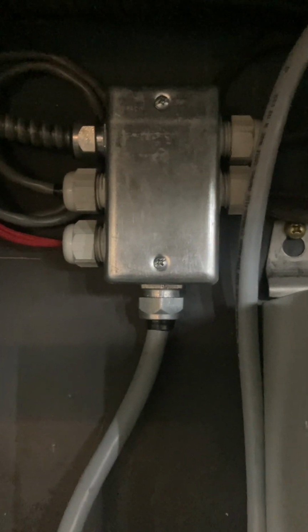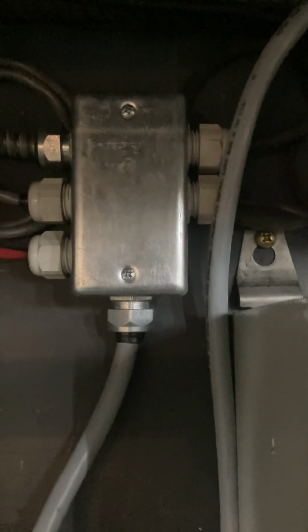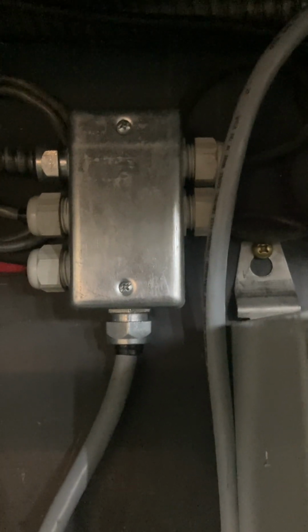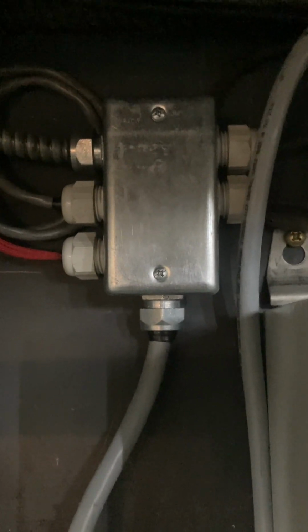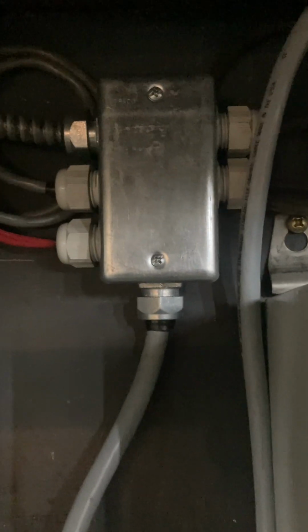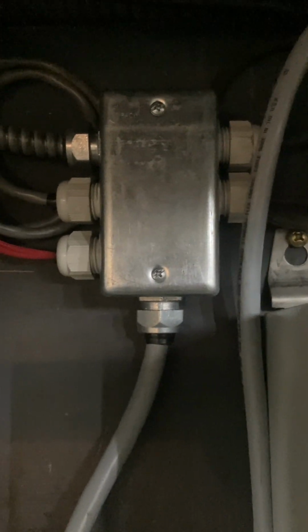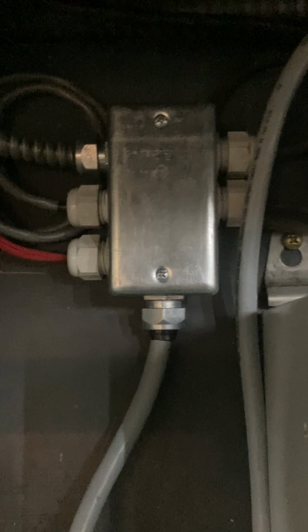Similarly, the limit switch wiring was bare. It just came in through holes punched at the top of the old contactor box, and I think this was the source of the problem. This area has been inundated by water and oil in the past, and bugs. These things would come in through the holes and coat everything inside: the electronics, the magnetic contactors, the relays. In winter, when you tried to open the dome shutter, you'd hear it buzz. What it was doing was cooking that polymerized oil, which had turned into varnish, until it softened enough to conduct electricity. So I think it was wise to just throw the whole mess out.